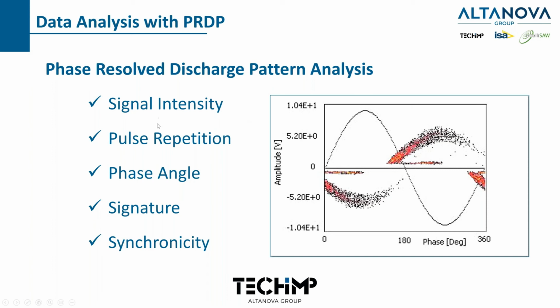Okay, so the first two, signal intensity, which is amplitude, and pulse repetition, which is how many times it's happening per cycle, will determine if it's dangerous to that asset. And then the phase angle, where it's happening in the cycle, and the signature, which is this pattern here, where every little dot represents a partial discharge, and they develop patterns, as you can see. And being synced to the circuit will help us identify the type of discharge.